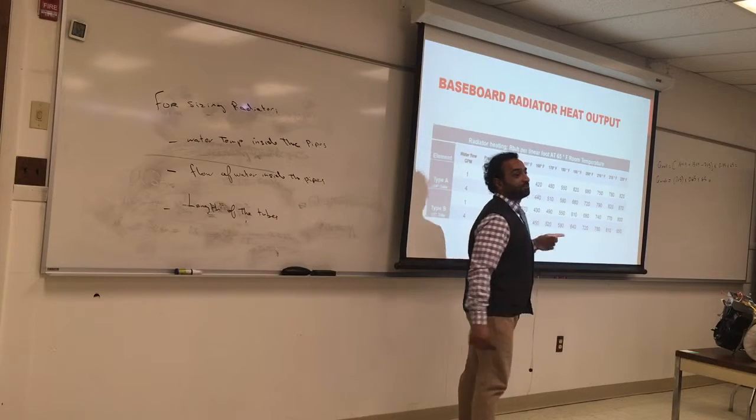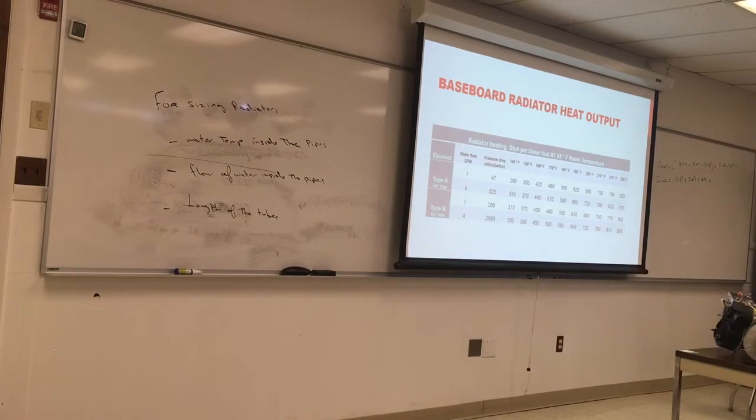So the pressure drop. Why is the pressure drop important? Because you need to know how much pressure is needed to account for the drop. Excellent. And that will affect your pump size. If you don't have the proper pump size, it's not going to push through all the radiators. At some point, it will crap out. There's no water flow, no heat. The system is ill-designed, and somebody has to go and do a quick fix, and probably it's not going to be done nicely, because you're going to have to add a pump. The pump's going to be oversized. So it's better to get things done right the first time.